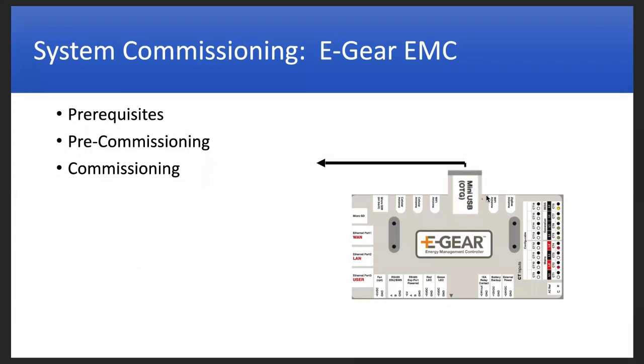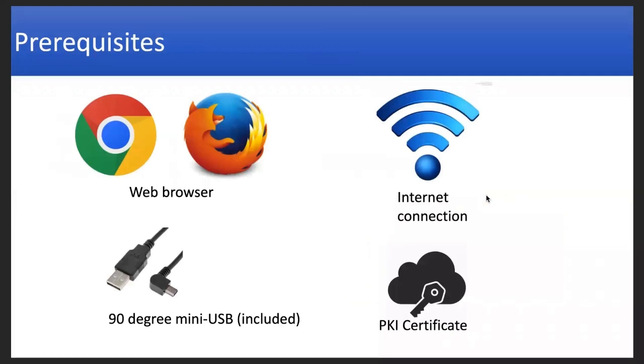What we're going to cover here, or look very briefly at, is some of the commissioning steps: the prerequisites, pre-commissioning, and then the actual commissioning itself. As a prerequisite, you're going to need a laptop with a web browser on it. Obviously, we recommend Chrome. Firefox also works. It does not work with Internet Explorer, so I recommend Chrome as the browser that you use. Obviously, you'd need an internet connection to set the system up, as well as have it connected for continuous monitoring. There's a 90-degree mini USB included with each system to connect your laptop to the controller, to the EMC, and configure it to commission the system.